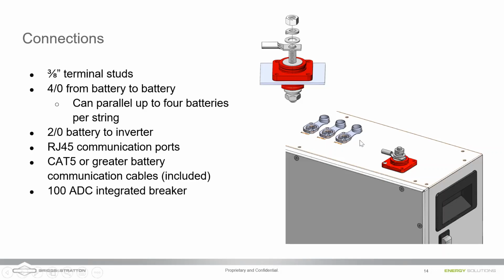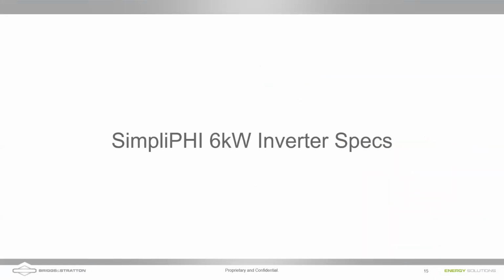The RJ45 communication ports take Cat5 cable or greater, pretty simple there. We actually do include the Cat5 cable for battery to battery connections. And I believe that's about 4 feet, but the communication cable from the battery to the inverter, that one is not included because it's going to be a specific length that we are not going to be able to guess. So again, we'll come back to wiring in more detail on the battery. But for now, I want to talk about our inverter and the specific specifications.